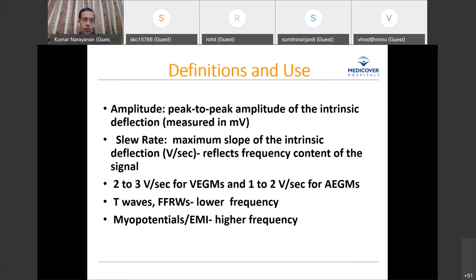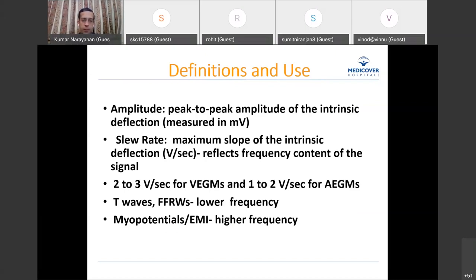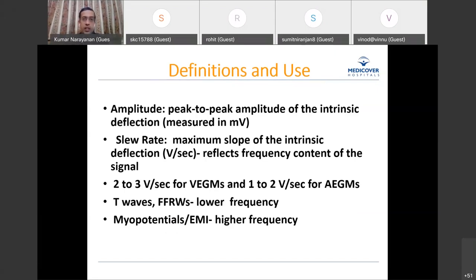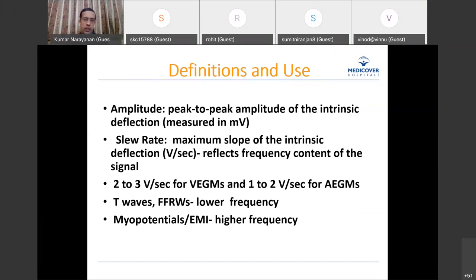Ventricular EGMs typically have a slew rate of about 2 to 3 volts per second; atrial EGMs are about 1 to 2 volts per second. Unwanted signals like T waves or far-field R waves have lower frequency content. Myopotentials or external electromagnetic interference have much higher frequency. Since signals of interest belong to a particular frequency range, this helps the pacemaker be selective about what signals it responds to.